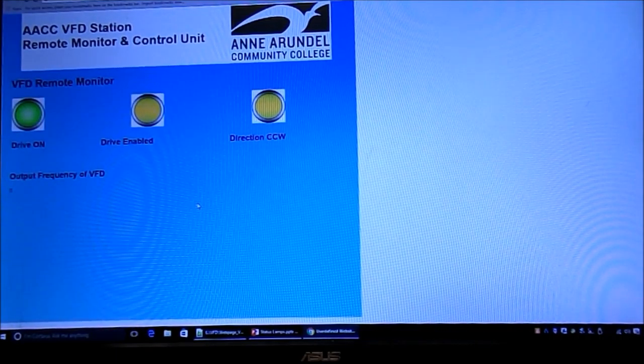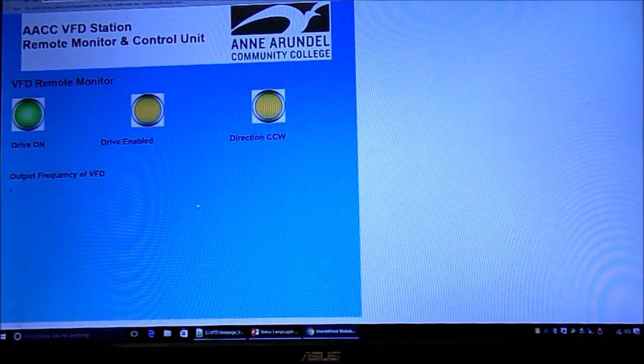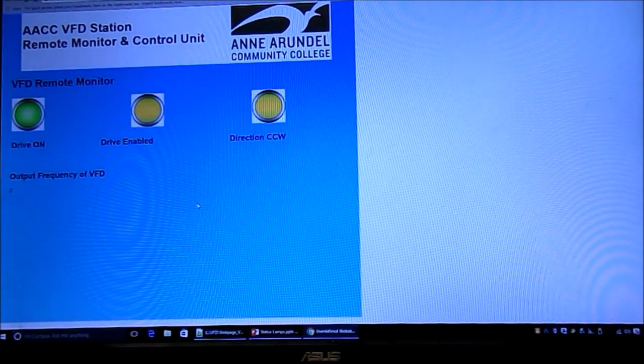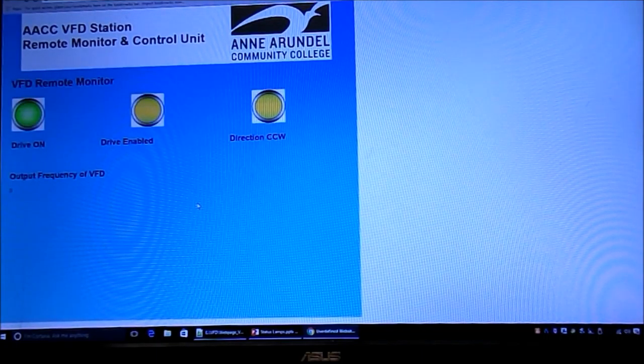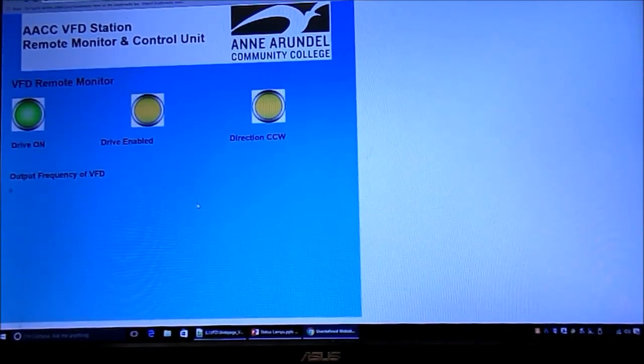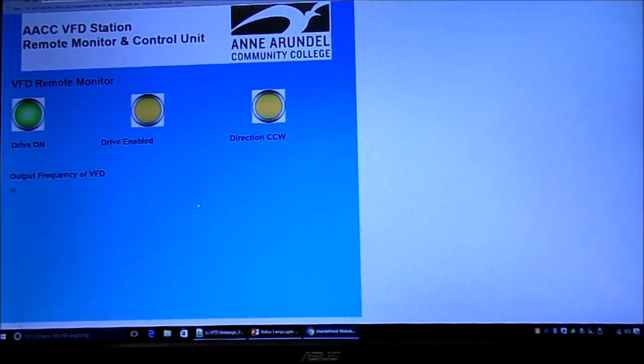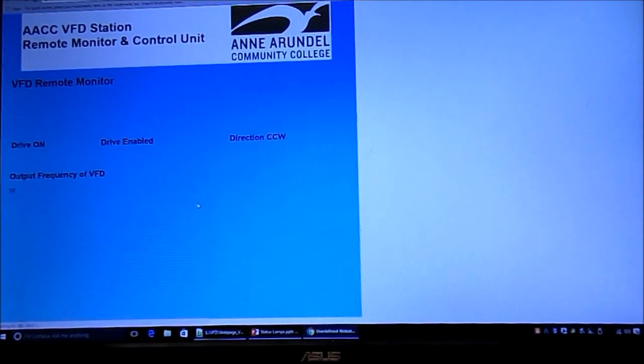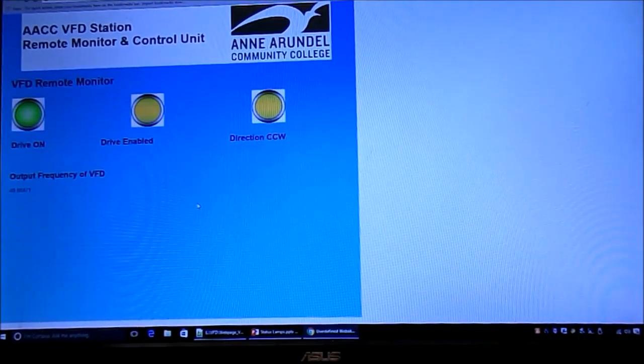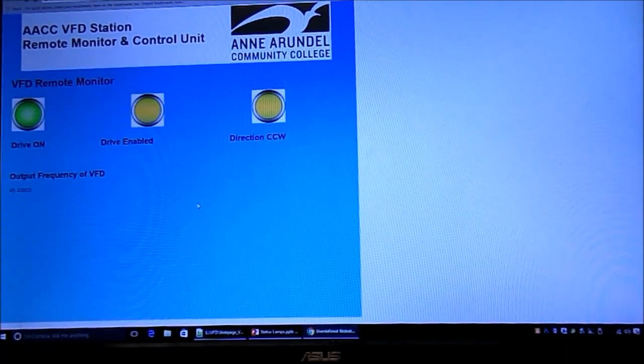Now the drive has started but we haven't put in our frequency yet. When it blinks we have it all ready to go. Now we'll go to our speed control menu and put in a frequency and start off with 50 hertz. Now we're running, and hopefully when we come back you can see it's 50 hertz right there. We might want to make it a little bigger at some point. We can also adjust it on the HMI. Here we're going down in frequency, and right now it's about a little over 45. When it comes back it says 45.4.